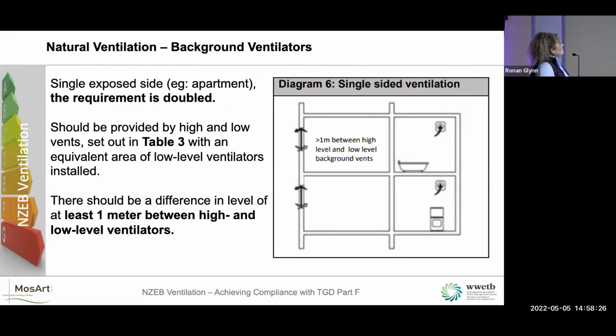I suppose the really interesting one for natural ventilation is when you have a single-sided dwelling. So where you've only one exposed facade, you have to double the requirement. So you work it out and then you have to double it. It also has to adhere to the regulations set out in table three. So it says that you must have high background ventilators and low background ventilators, and there must be 1 meter between the two. So let's have a little example of that.